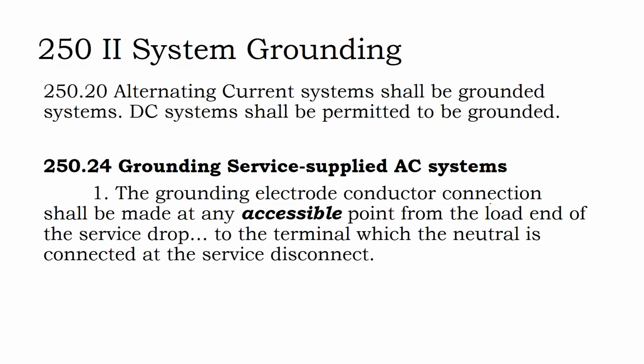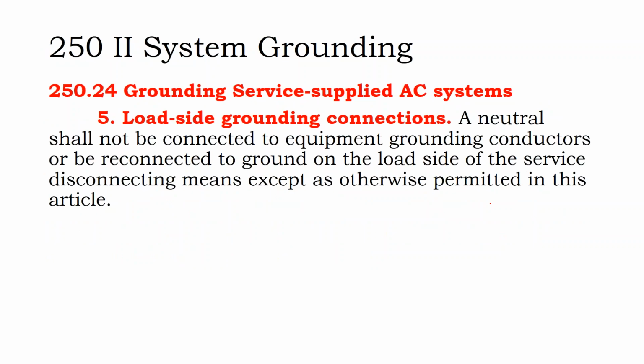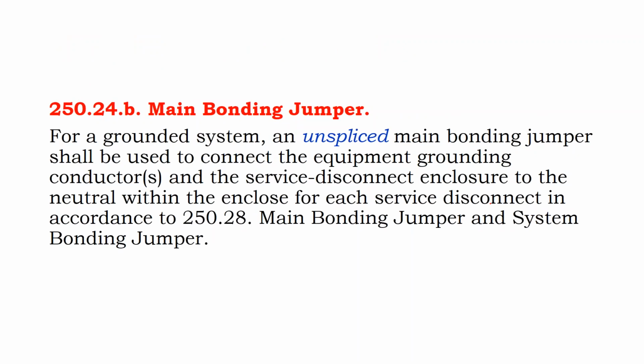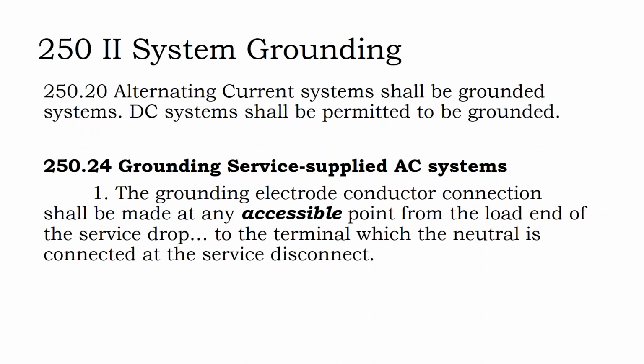On the load side, a neutral shall not be connected to equipment grounding conductors or reconnected to ground on the load side of a service disconnecting means unless otherwise permitted. So all this talk of bonding the neutral to ground, generally speaking, you don't do it. We've already talked about it, so I'll keep going. There's an illustration a little later. Then we start getting into unspliced bonding connections. An unspliced main bonding jumper shall be used to connect the equipment ground conductor and the service disconnect enclosure to the neutral. So just that one section where you're connecting the neutral to ground, that needs to be an unspliced conductor.